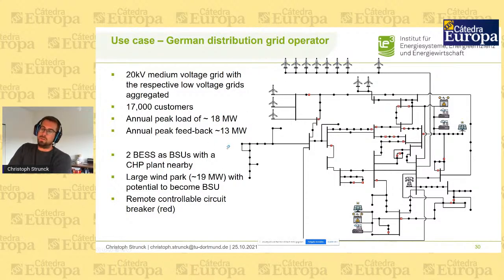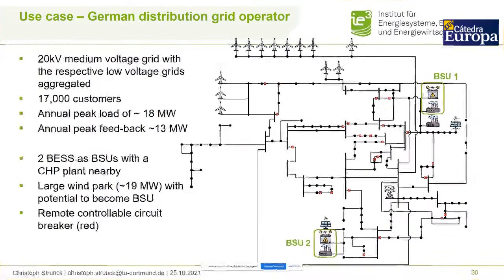So you see a lot of renewables are installed in that grid, namely the 2 wind parks in the northern part and in the western part. There are also 2 possible black start units: 1 battery storage here, and 1 battery storage with a CHP plant at the lower part of the grid. Not yet available, but possible in the future, is the wind park in the north, which could also become a black start unit.